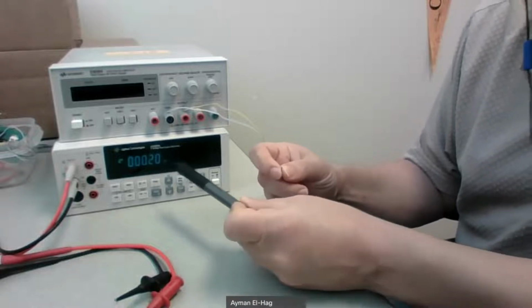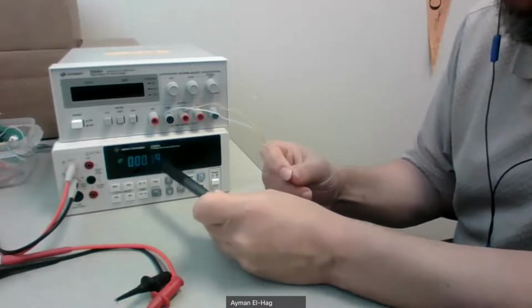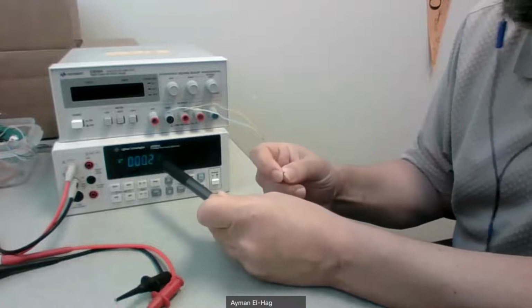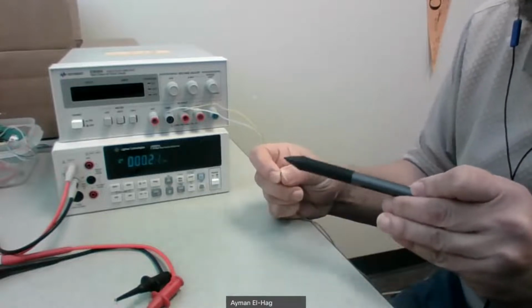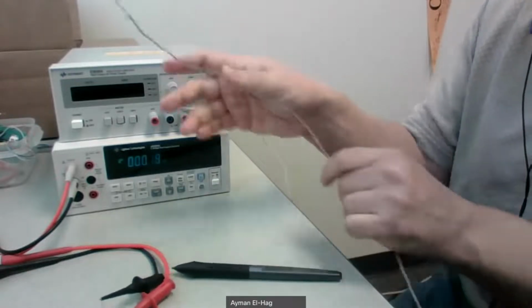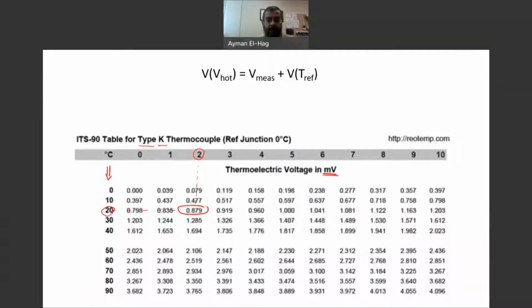The point is we want to see how to convert this voltage, let's say 0.2 millivolt, into the temperature at the tip of the thermocouple. To do that, we need to use the data sheet of the thermocouple. The one we are using here is called K-type. There are different types of thermocouples, so we have to know which type we are working with in order to do the conversion.